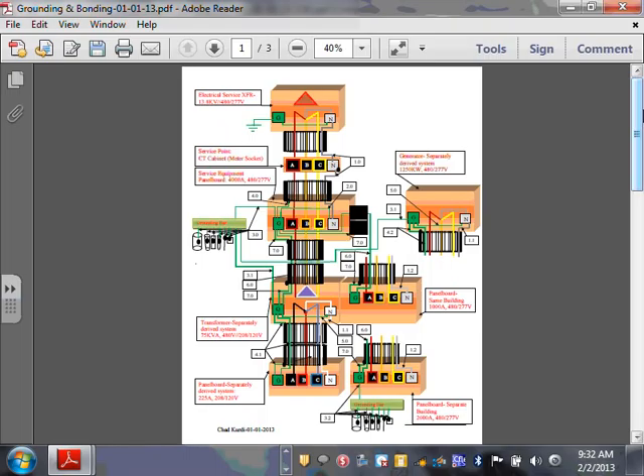The only thing that's not here, and please correct me, all of you are masters, journeymen and engineers, is that this will probably be 80% of what you need about grounding and bonding in typical buildings. What's not here, as I stated, is agricultural buildings where you need an equipotential plane, and swimming pools with bonding of the belly of the pool. Hospitals, a little bit of bonding the panels in hospitals. It's not here, but this represents probably 80% of what you need in a typical commercial industrial building, from a 200 amp 240/120 service all the way to a 4,000 amp 480 or 208/120 service. Any comments, guys? Did I forget anything dear to your hearts that's not here?